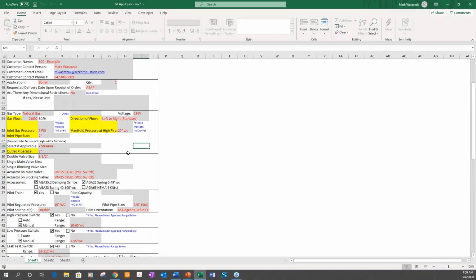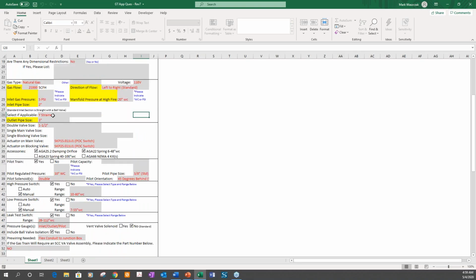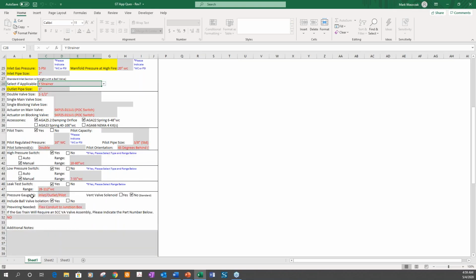Now, I took the liberty of filling out all the information. Very similar format as the other program, where you select what type of gas you have, what the flow is, your inlet gas pressure, your pipe sizes. Some additional questions this will have is if you want a Y strainer or inlet drip leg. You go through, fill out all the information, and you can use the sizing program to determine what information you have to input in here. Some additional questions it will ask is whether or not you want pressure gauges and also if pre-wiring is needed.